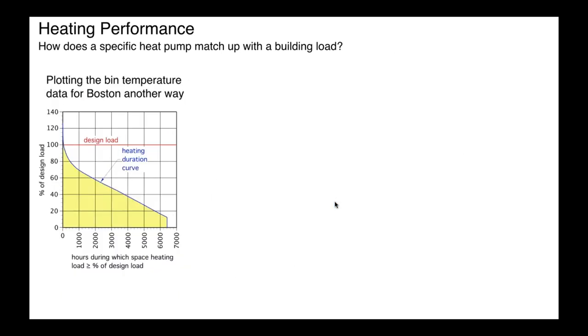Now, this next graph is another way of looking at that bin temperature data. It's called a heating duration curve, and you're plotting the percent of the design load on the vertical axis, or you can also plot directly BTUs per hour of the design load. Okay, so it could be a percent. I left it as a percent just so it would apply to, in theory, any building, okay? And on the horizontal axis, you're showing the hours during which the space heating load is greater than or equal to a given percent of design load, okay? So we have hours as our units on the horizontal axis.